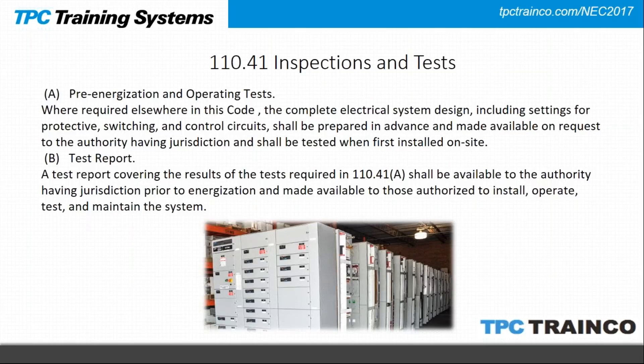A new section covers pre-energization and operating tests — essentially commissioning equipment. Where required elsewhere in the code, the complete electrical system design and settings for protective devices — ground fault settings, switching control circuits — must be prepared in advance and made available on request to the authority having jurisdiction. The system must be tested when first installed on site, and a report covering the results must be made available to the AHJ. This ensures all settings are correct and safety is in everyone's mind.